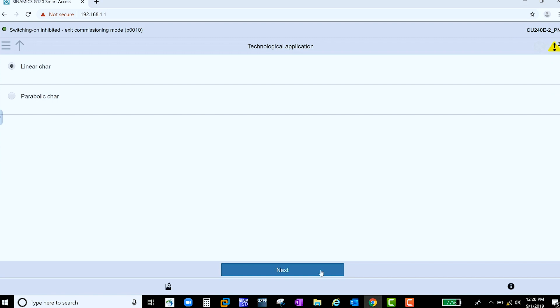Here you select your technological application. Do you have a linear characteristic, such as a simple conveyor belt? Or do you have a parabolic characteristic, such as a simple fan or pump?